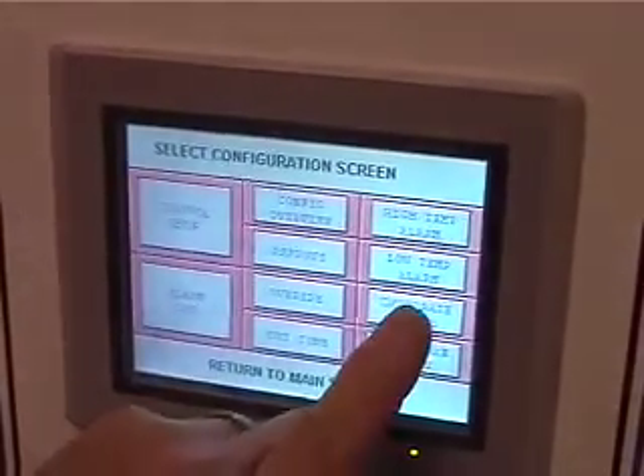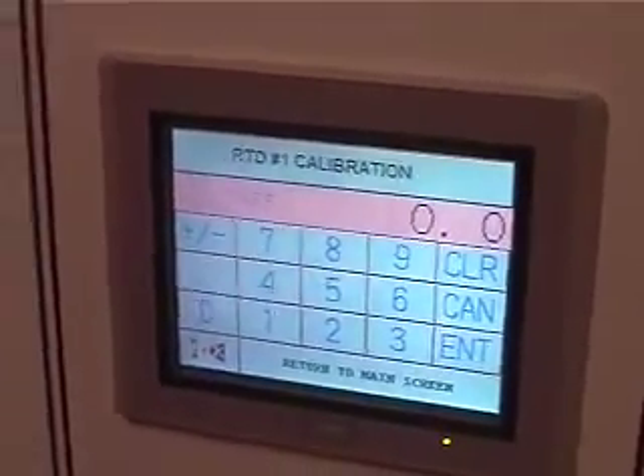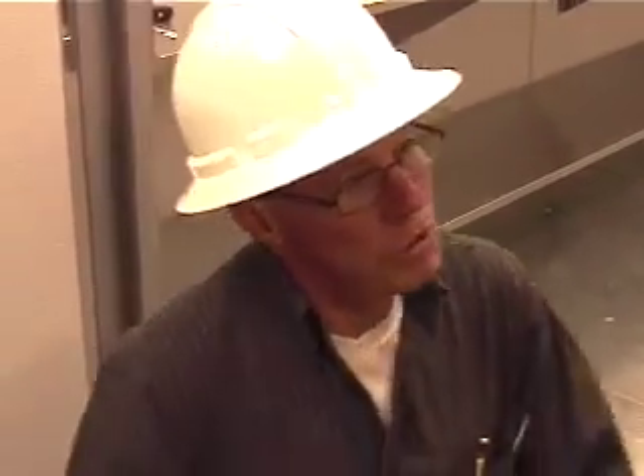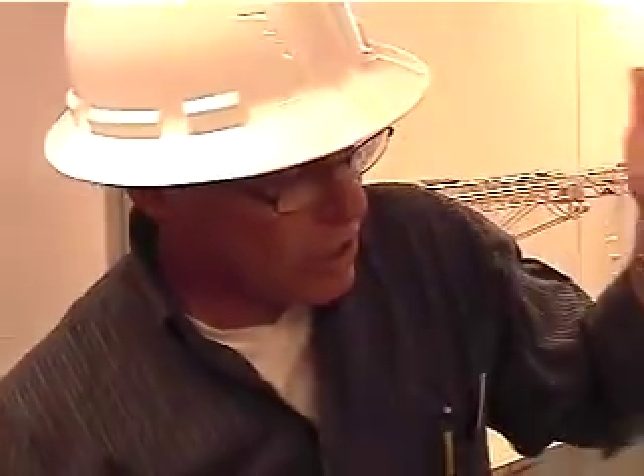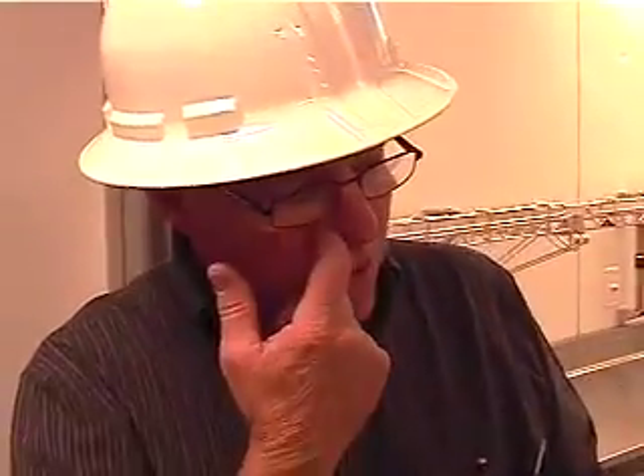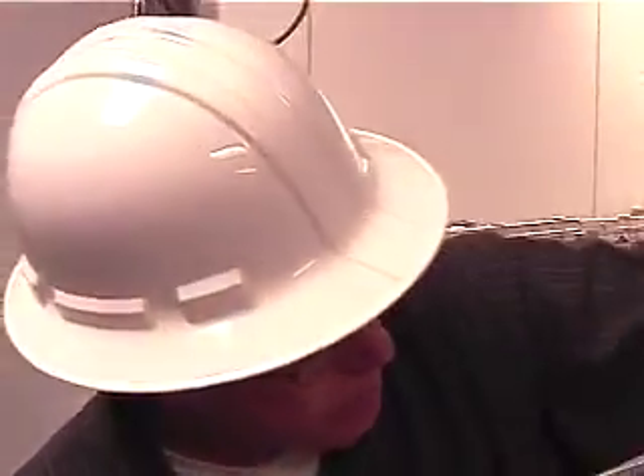Calibration. These RTDs calibrate just like Honeywell or any other controller out there. It's an offset calibration, and you have two of them. You have number one, the one that's in the coil, and number two, the one that's out here. We found the best way to do this is to shut the room off, shut the fans off, just shut the room down, put a little switch on top if you want, and then use your Fluke meter, whatever you're using to calibrate that. Get it near the RTD and then set it up that way.